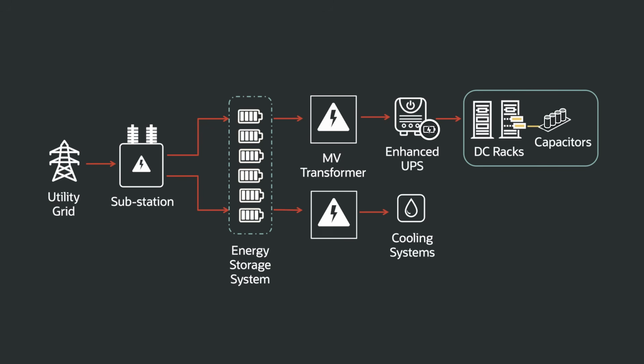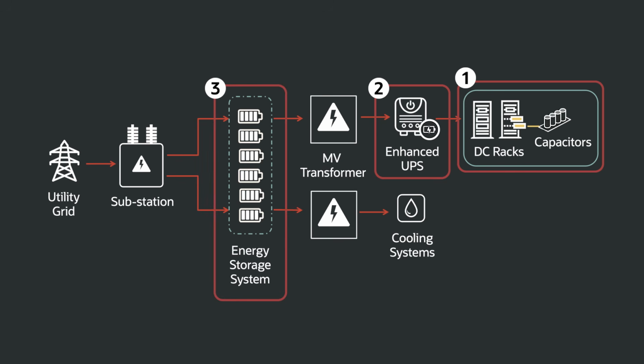The third one is the energy storage system. Within that, there are 3 levels: one is within the rack, sometimes called a supercapacitor shelf or capacitor within the rack itself, which can help dampen sub-second oscillations. Since you can't put a lot of capacitor shelf within the rack, you don't have much room, so it can help dampen maybe a few seconds of power oscillations. The next place to put energy storage is an enhanced UPS, where you can add additional storage. The third is at the campus level, where you can deploy an energy storage system to dampen the power swing so the utility doesn't see it.